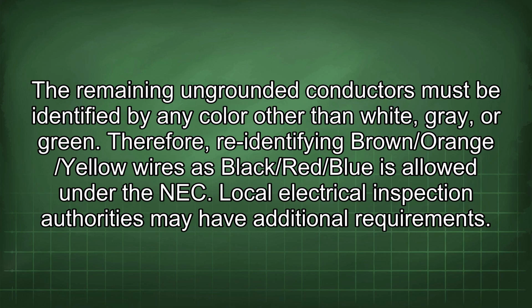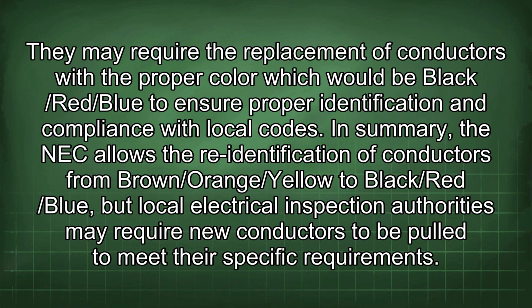Local electrical inspection authorities may have additional requirements. They may require the replacement of conductors with proper color, which would be black/red/blue, to ensure proper identification and compliance with local codes. In summary, the NEC allows the re-identification of conductors from brown/orange/yellow to black/red/blue, but local electrical inspection authorities may require new conductors to be pulled to meet the specific requirements.